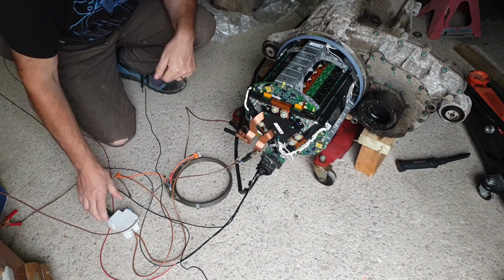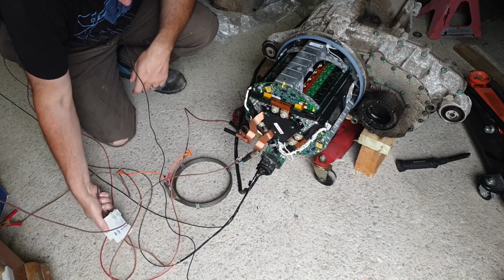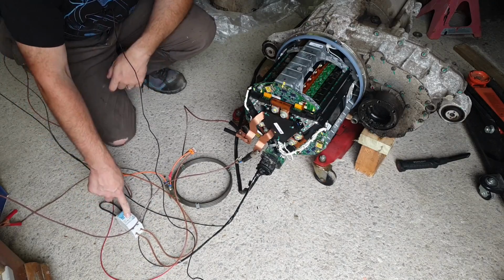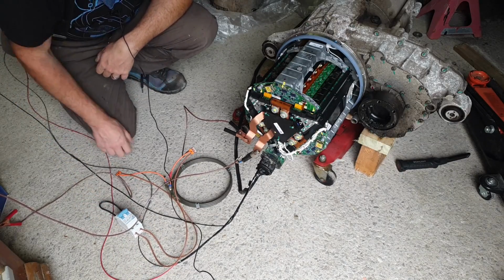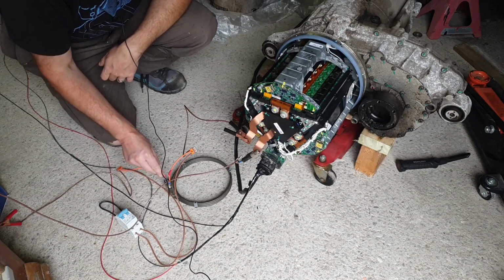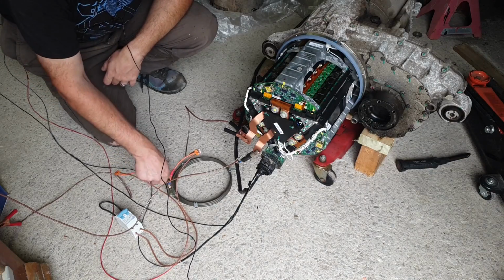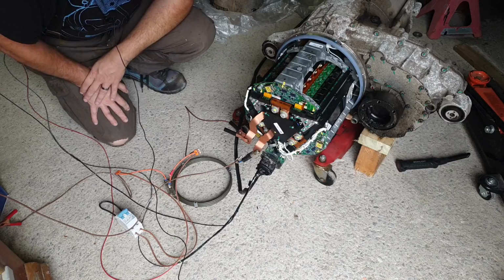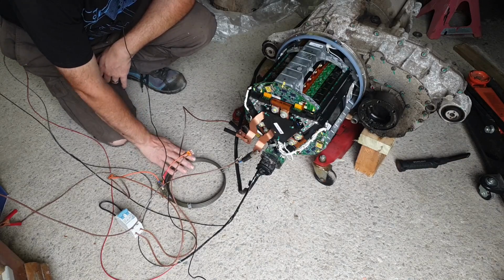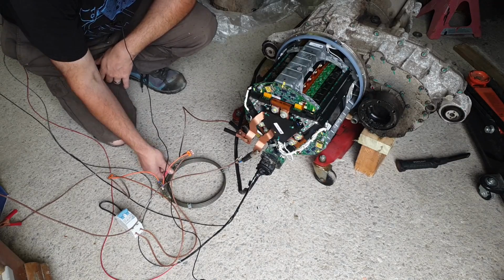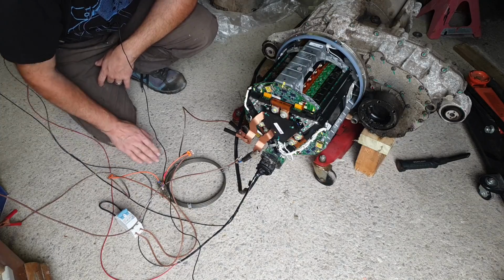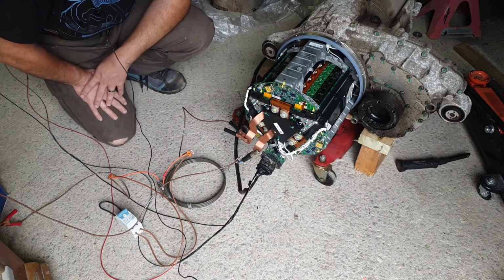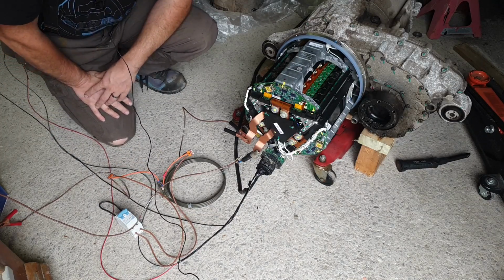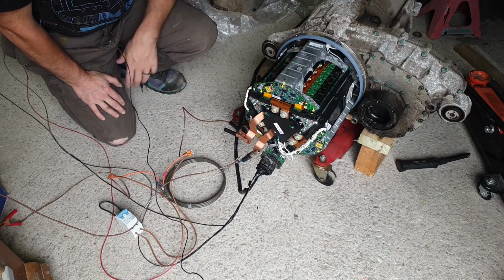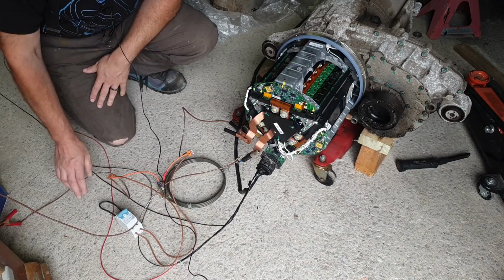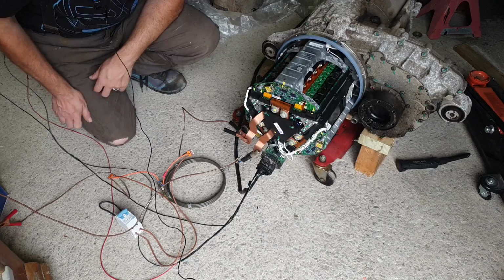So that's on. For my first power up, I want my circuit breaker off. This means any of our testing voltage must pass through the heating element. So when we first connect this, the heating element acts as a kind of crude pre-charge, letting us pre-charge our DC bus capacitors with the circuit breaker off.